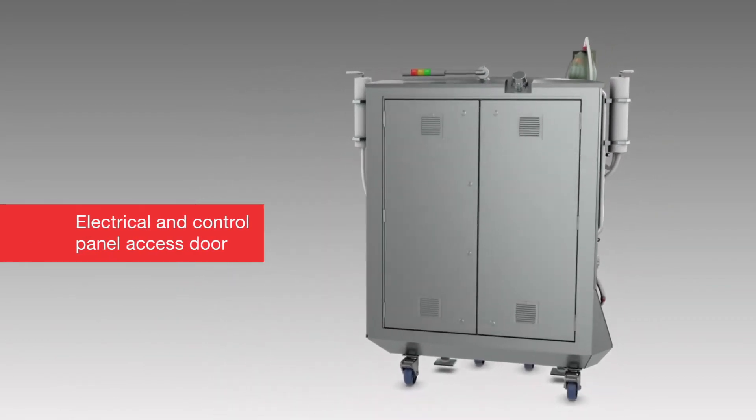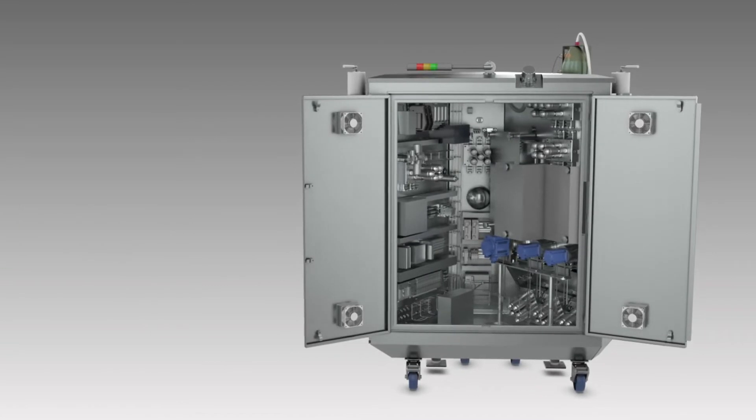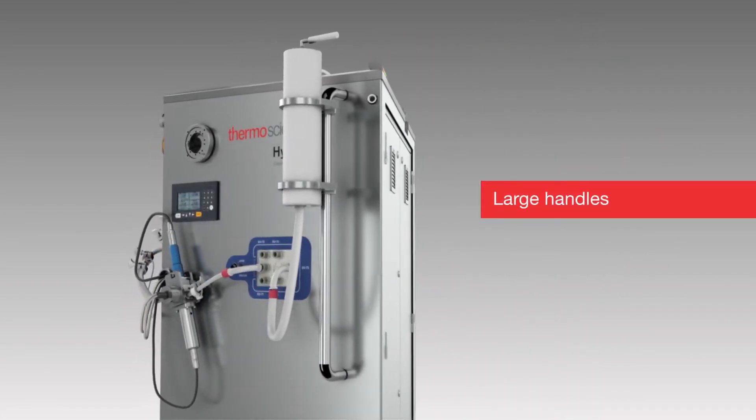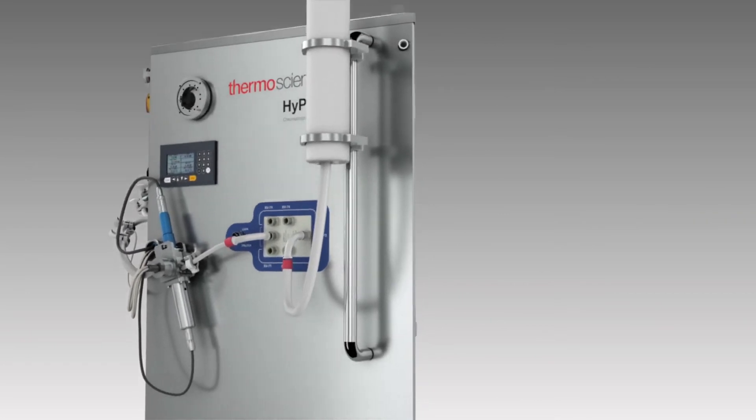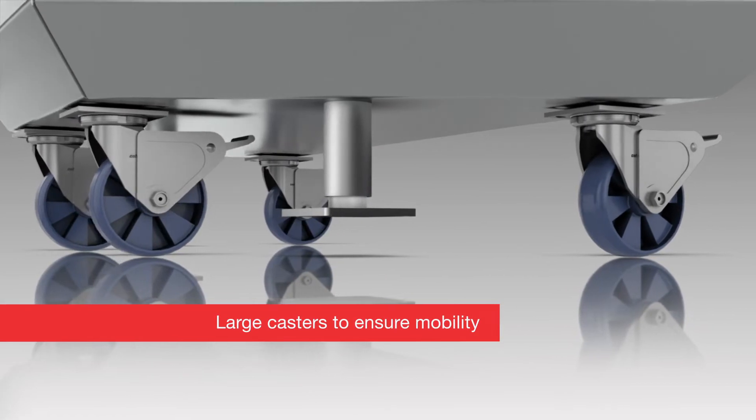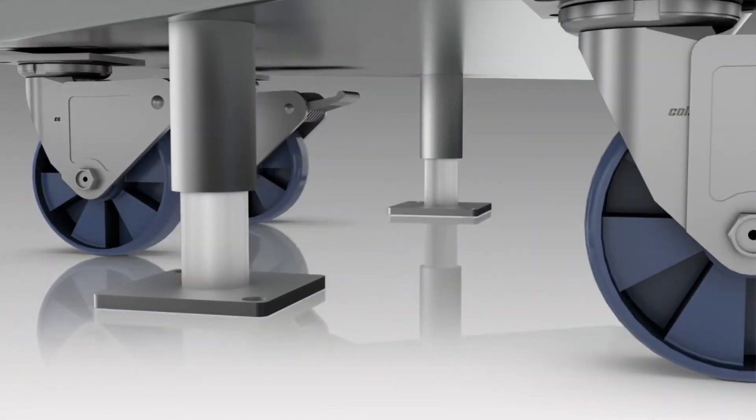Two large doors at the back of the unit provide access to the electrical and control system of the hardware. Large handles provided on the hardware help to move it safely and with minimal effort. To ensure mobility, large casters are used, specifically designed for use in clean rooms. The hardware includes leveling feet that can also be bolted to the floor for stability.